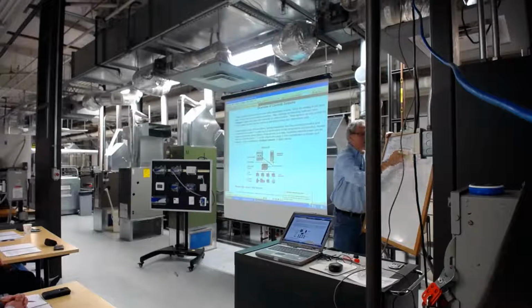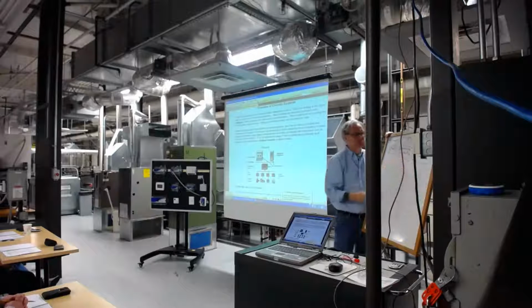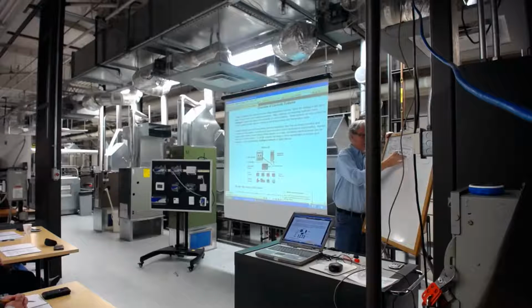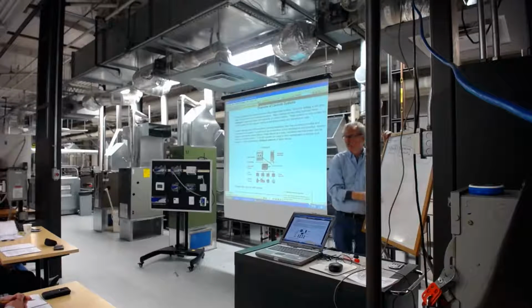So you've got these guys. These would be vendor dependent. So JCI or Andover or Siemens, they're all good people. They'd have these things called supervisory controllers. So this is the window into the system. These things here are actually high level. They're supervising the lower tier. There is logic in here. Okay? There's features like a weekly schedule, demand limiting, whatever features they want to have, trend logs and stuff like that. They're built in, and they're here. What they do is they oversee the lower level.